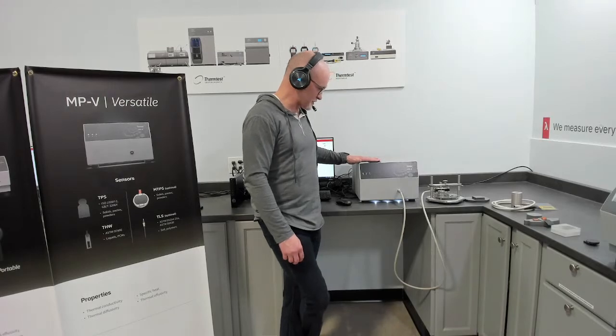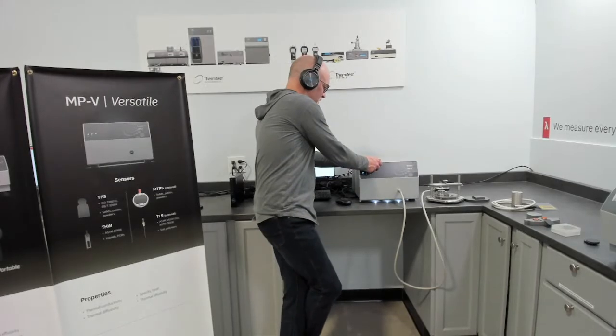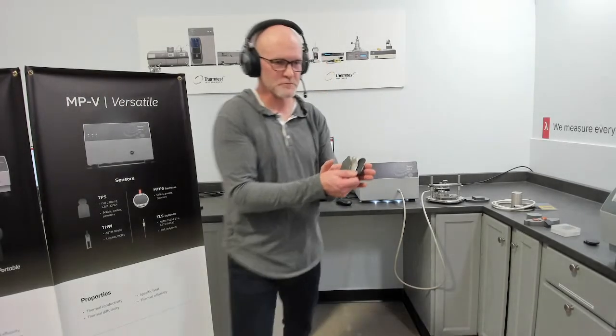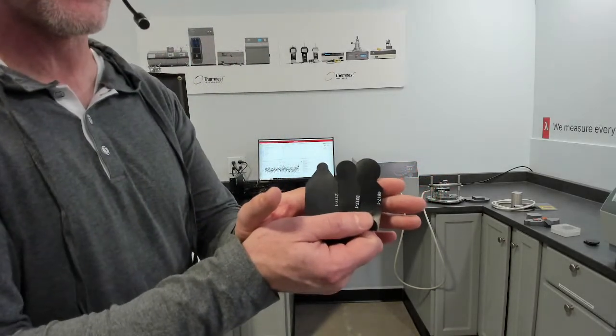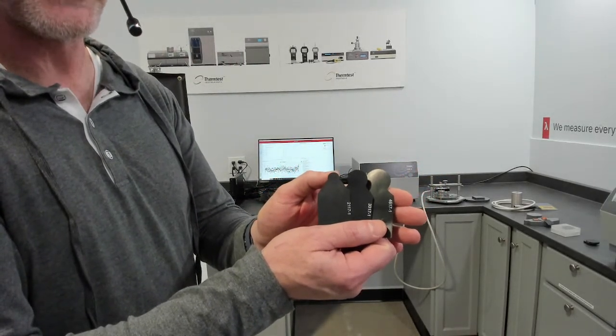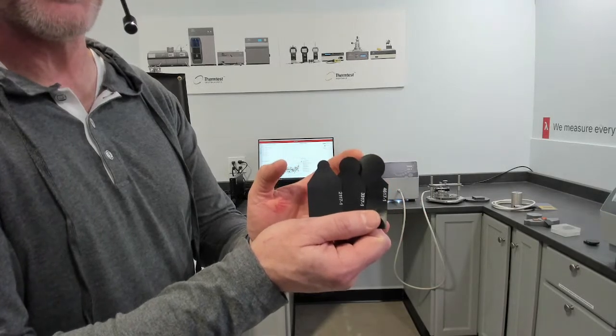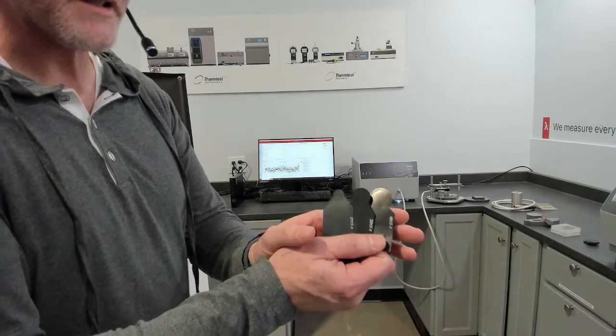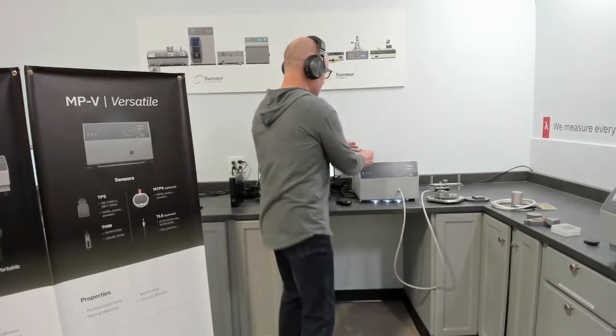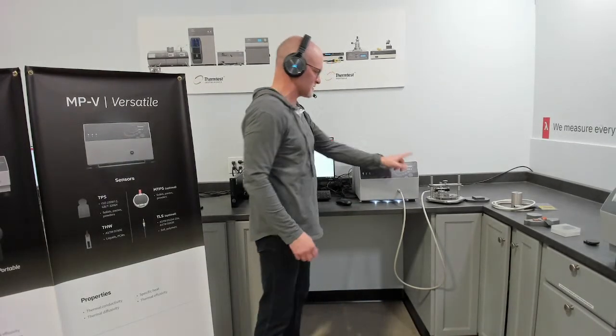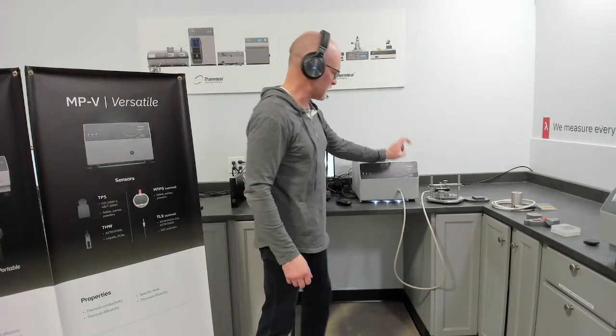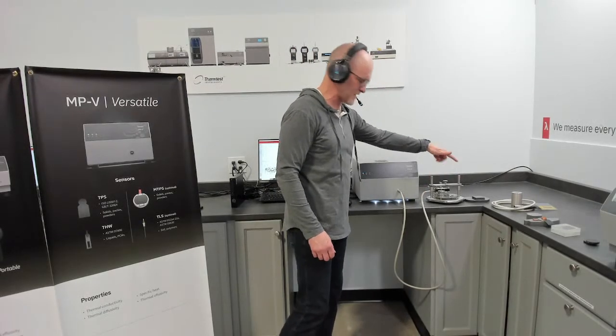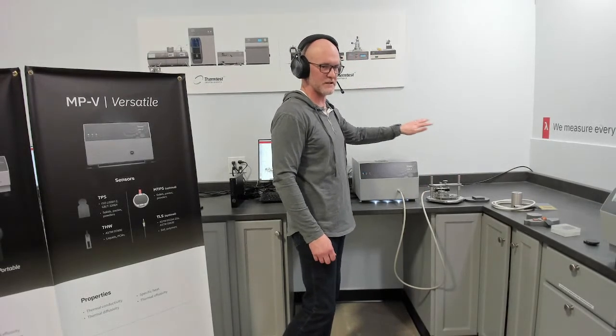It comes with, so that transient plane source method comes with 3 sensor sizes as the base package: radius 3.2, 6.4, and 10 millimeters. That comes with the basic package. None of our sensors require cables, because all of our adapters and connectors for the room temperature sample holder are quick connect, so you don't need cables.